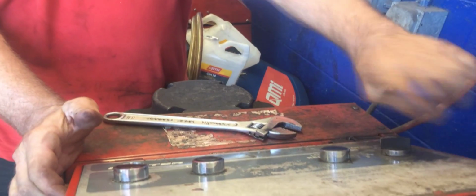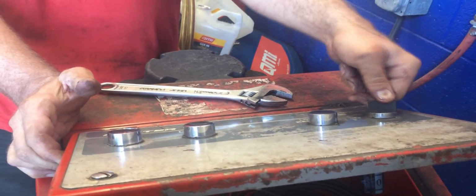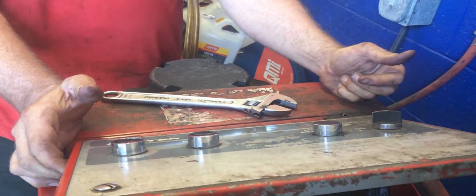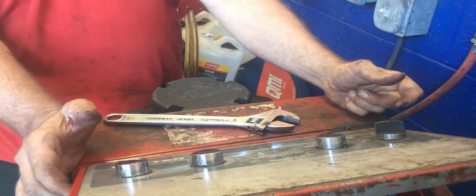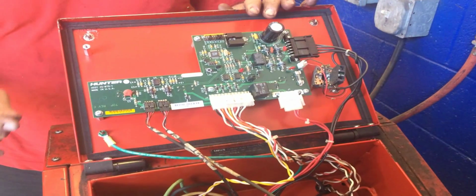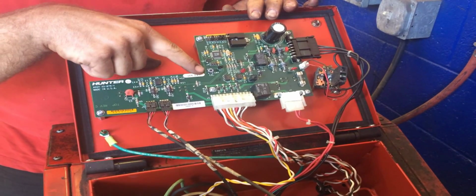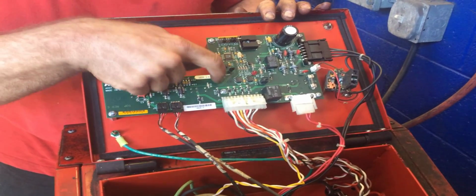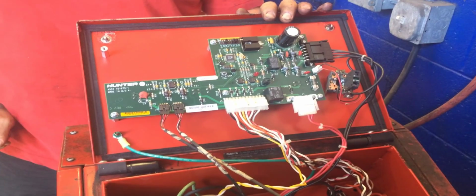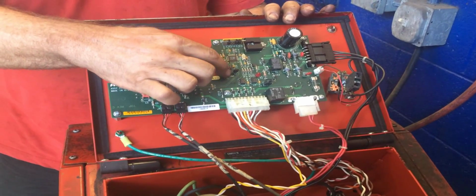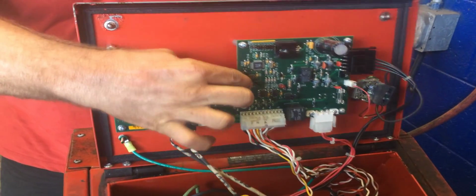Now the next step is, before you turn the power on, you have to have the power off at this point. You jump it, power's off. And there's a switch there, which is the cal switch, calibration. There's a CAL on the bottom of it. You hold that button in while you turn the power on.